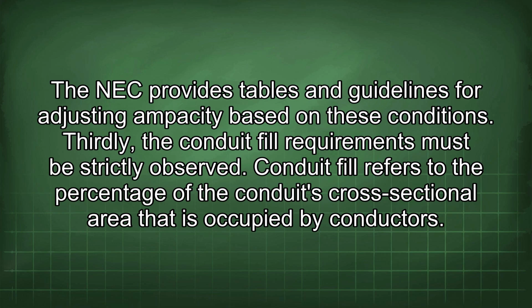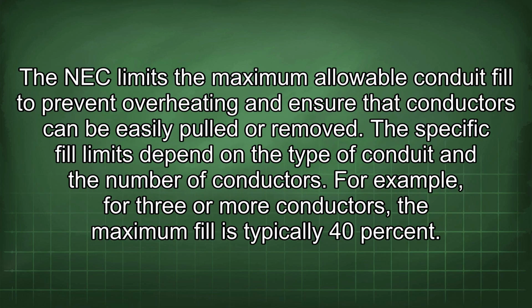Thirdly, the conduit fill requirements must be strictly observed. Conduit fill refers to the percentage of the conduit's cross-sectional area that is occupied by conductors. The NEC limits the maximum allowable conduit fill to prevent overheating and ensure that conductors can be easily pulled or removed. The specific fill limits depend on the type of conduit and the number of conductors. For example, for 3 or more conductors, the maximum fill is typically 40%.